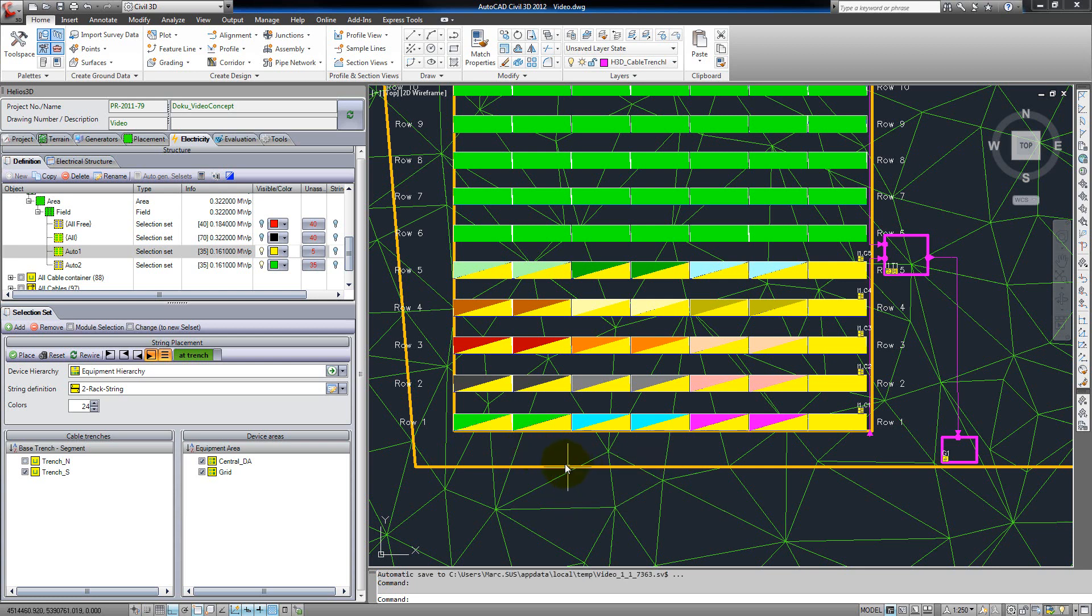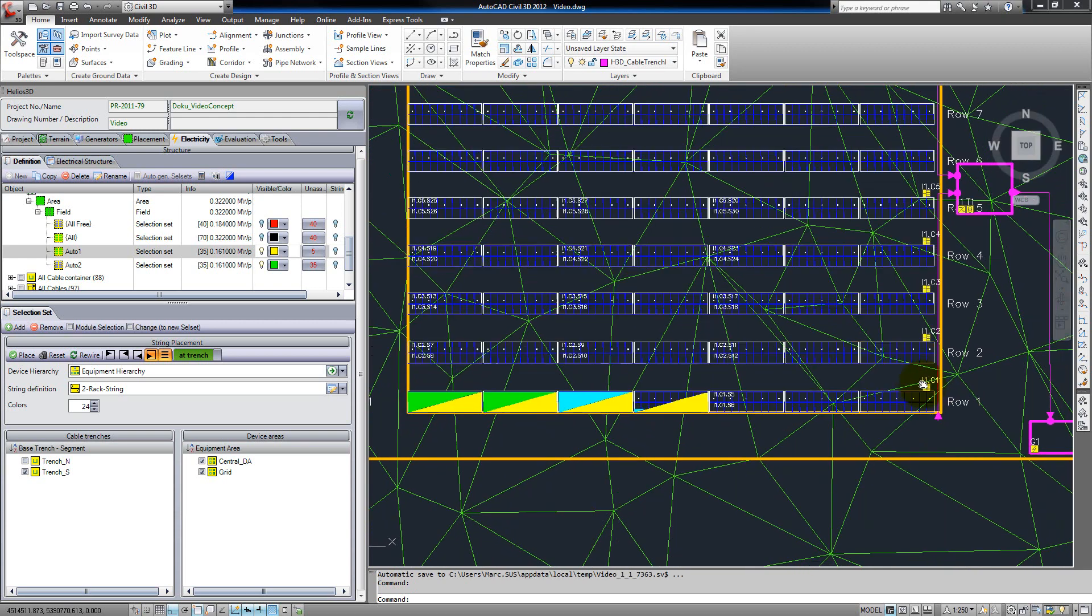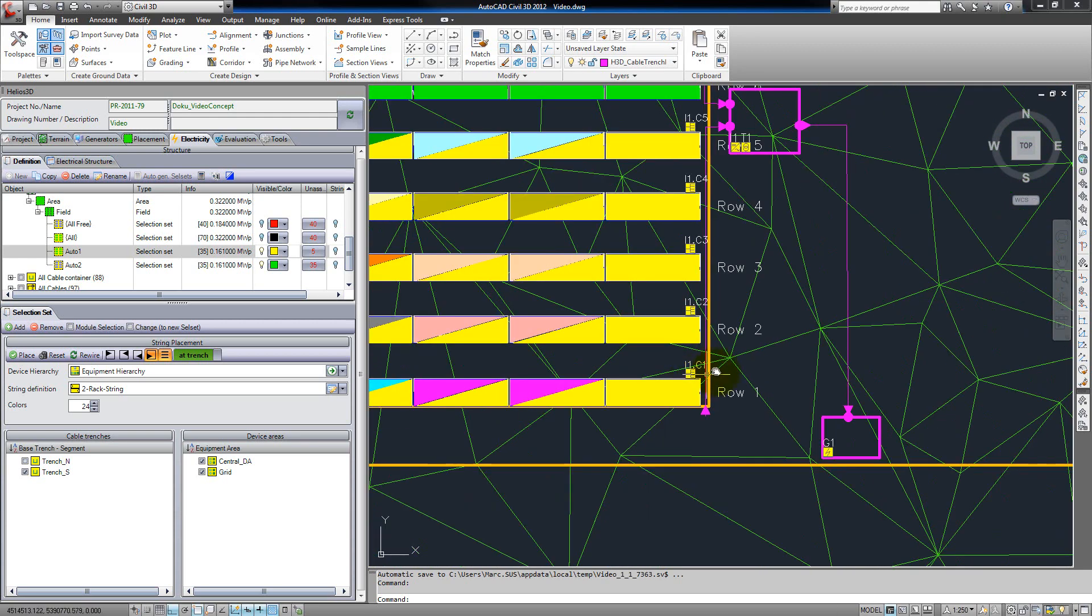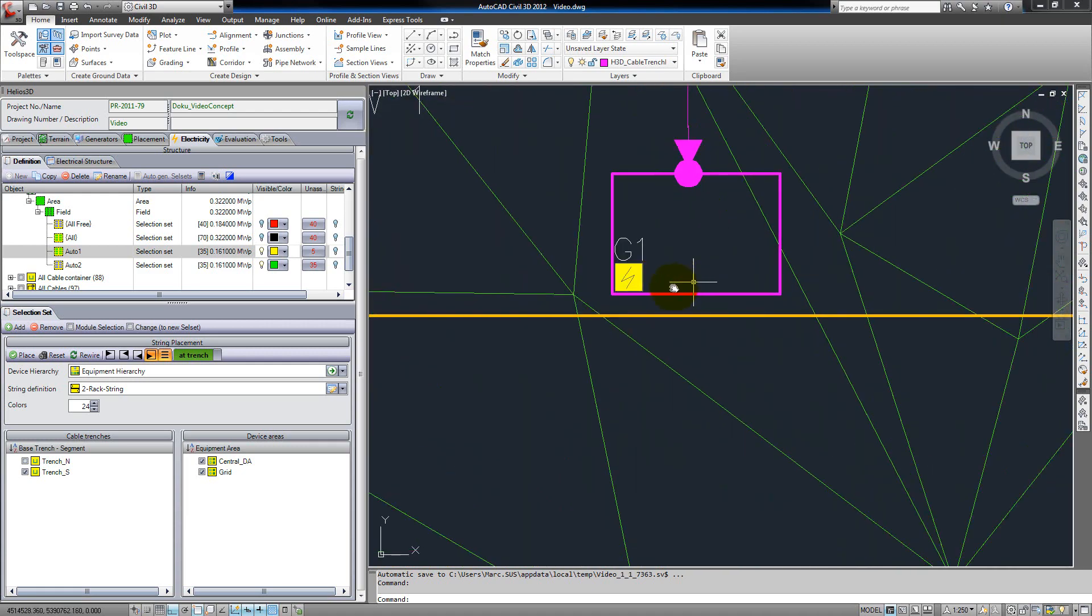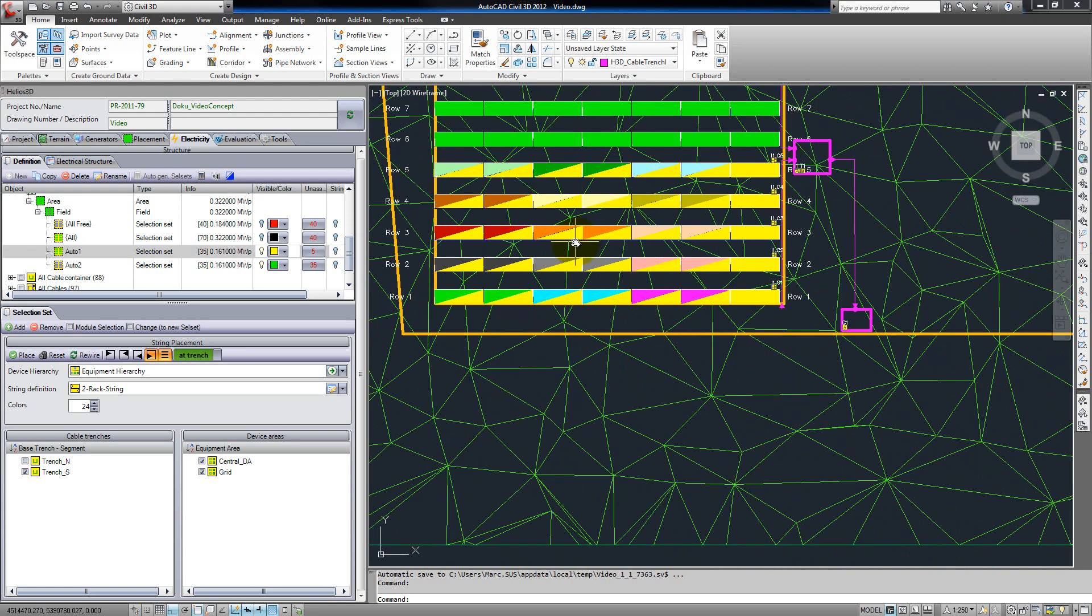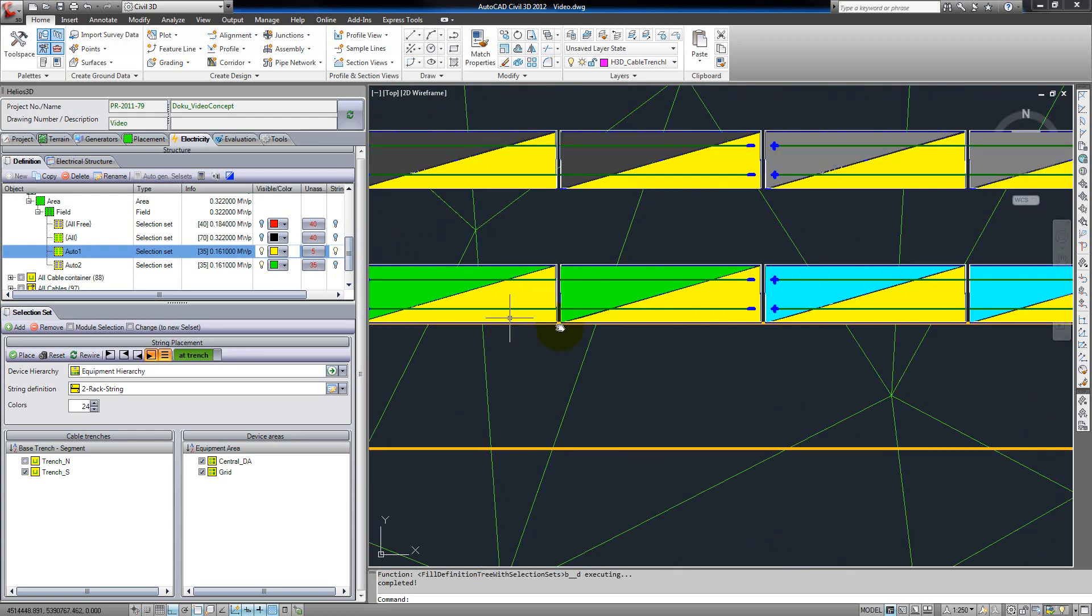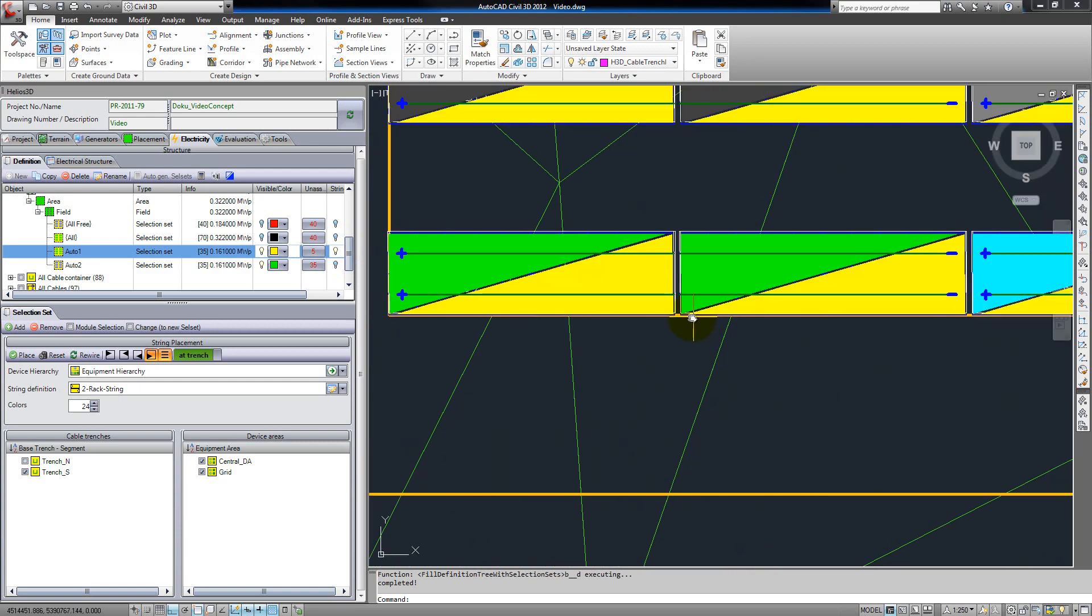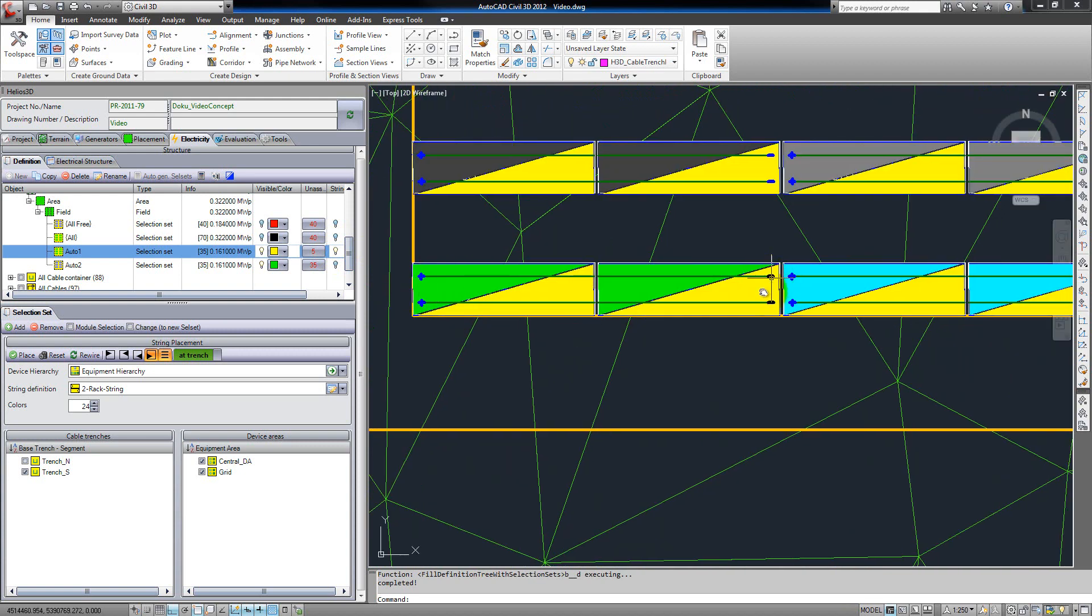Here we can see the results of the placement. The strings are displayed in different colors in the upper triangles, always running over two racks. The combiner boxes are placed at the end of the rows, always close to the cable trench. An inverter and transformer are in the first device area, and the grid connection in the second area. The string wiring is on an extra layer, and we can switch it on here, so we can see the string connection and the wiring inside the string.